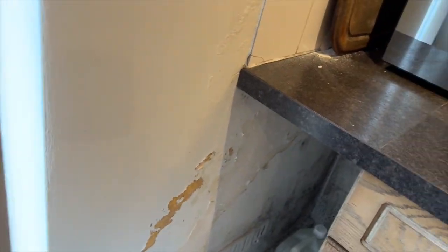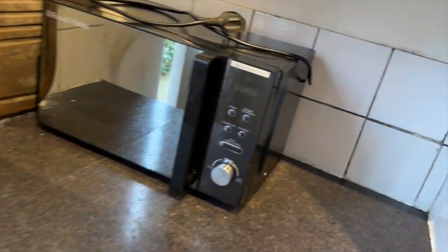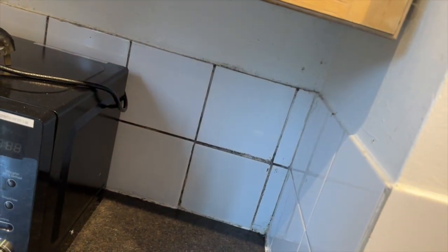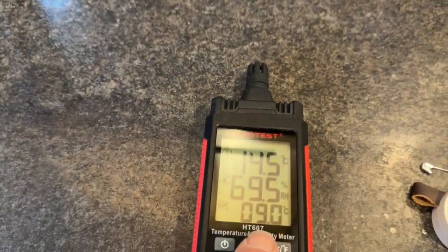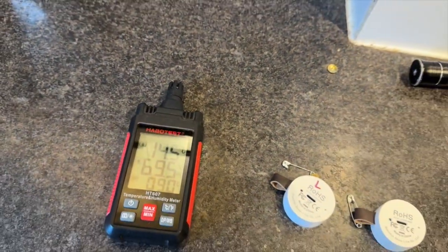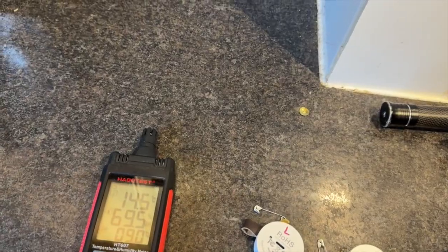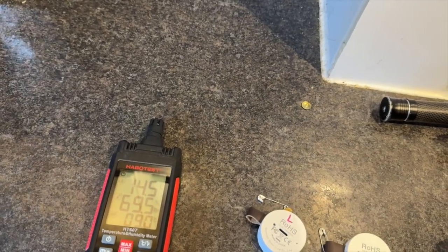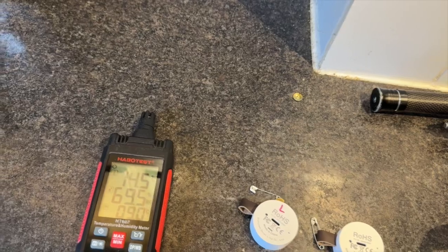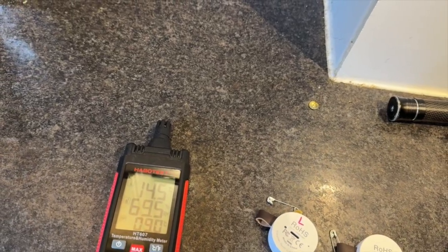But you see, you're getting mould growing in between the grouts, or in the grout, should I say, down there, around there. Mould grows where relative humidity goes above 85% for long periods of time. Relative humidity is caused both by high vapour levels, and we'll look at that. At the moment your vapour is showing 9 degrees centigrade. And it's also temperature. We haven't had people in here cooking for a couple of weeks, and also the door's been open quite a bit.